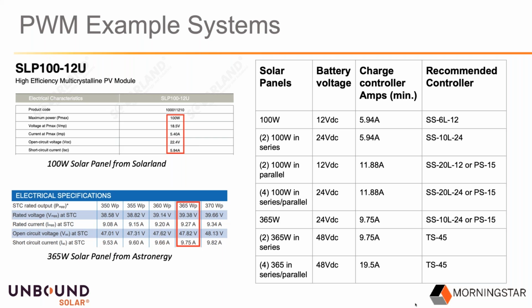I won't spend too much time going over this table. Oh, one note, for a 48 volt system, we had to go up to a TriStar controller because they can do a 48 volt battery bank, where some of the smaller ones like the ProStar do 12 and 24, and the SunSaver is only available in 12 and 24. So we had to move up to a TriStar controller for 48 volts, even though it wasn't a high current requirement where we really needed the 45 amp controller.